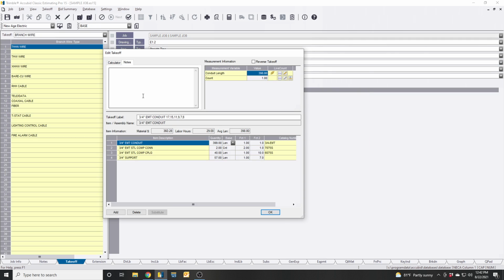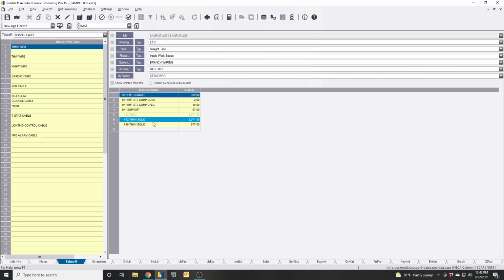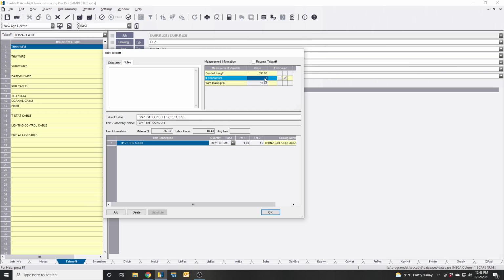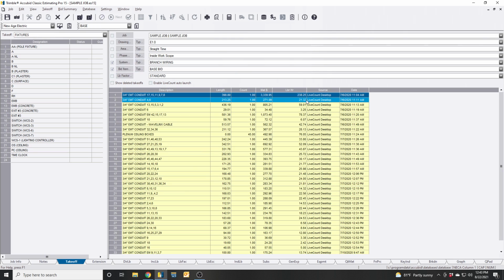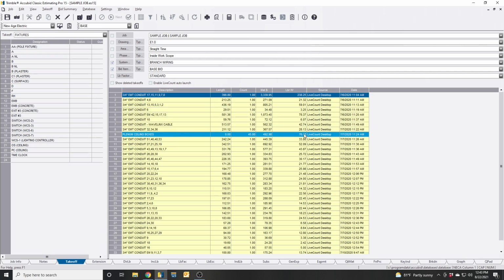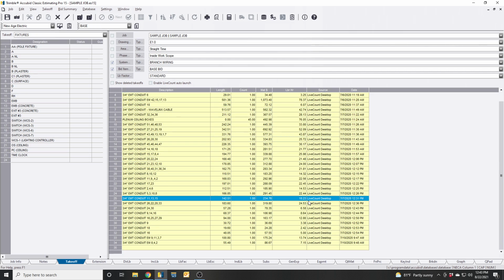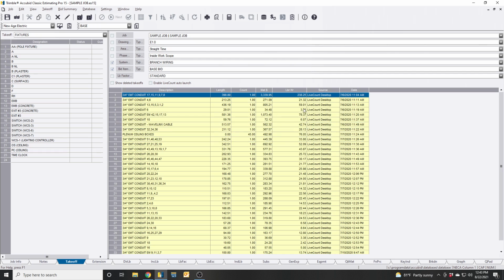Well, when I was taking this off, let's say by accident, something was wrong on my keyboard, or I had fat fingers, and I put 77 conductors in this one pipe. So now I've got 238 hours. If you look at the rest, they're all 20s and 30s and 40s. So those look right, but this one jumps out.